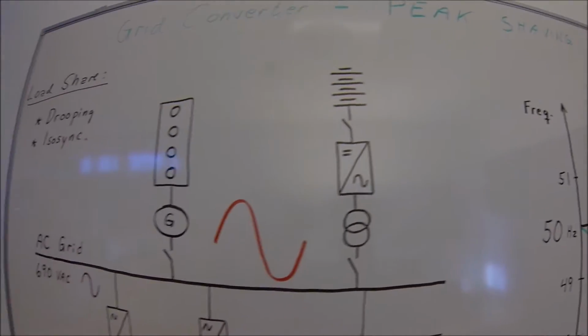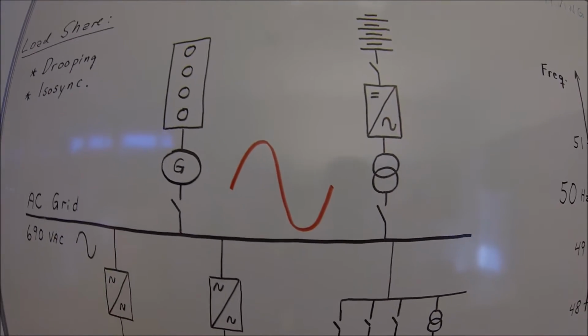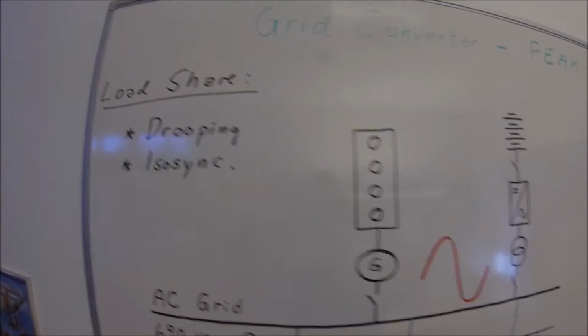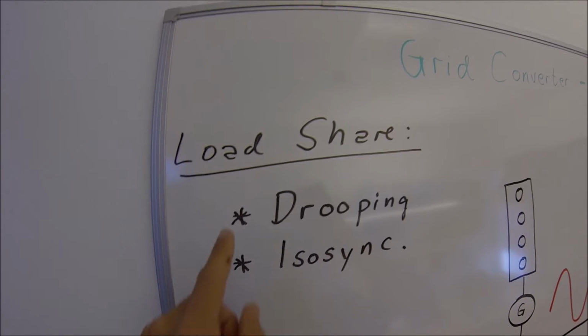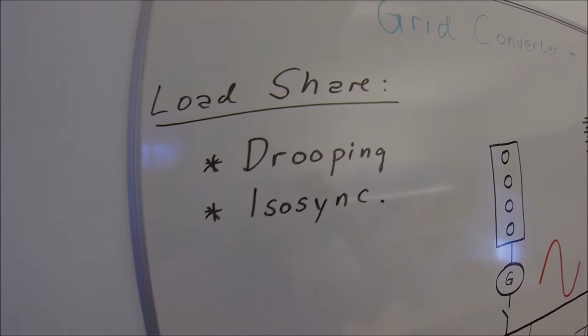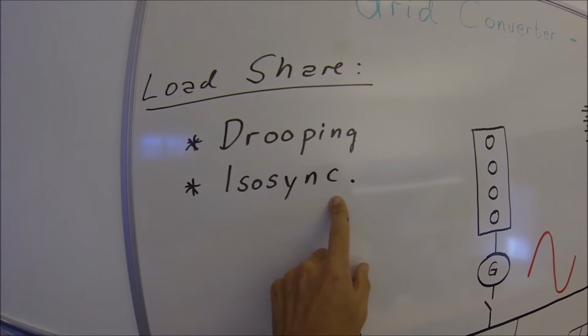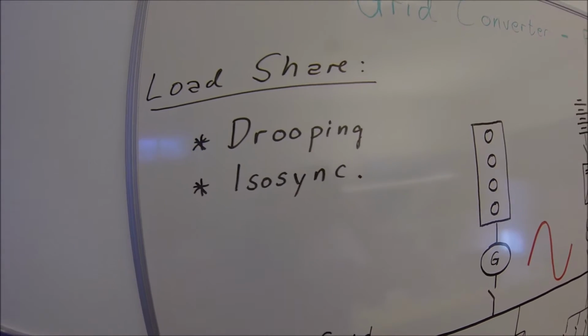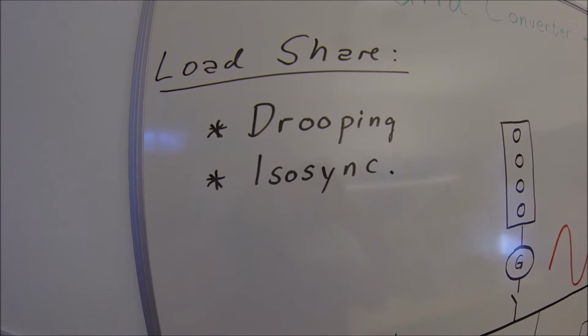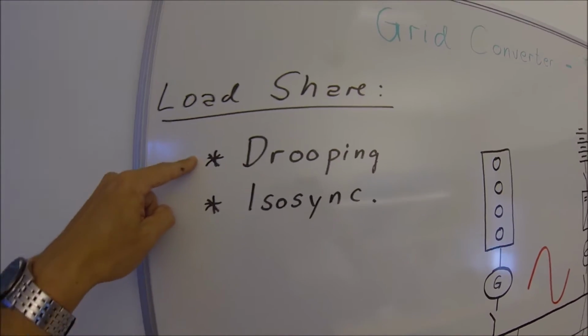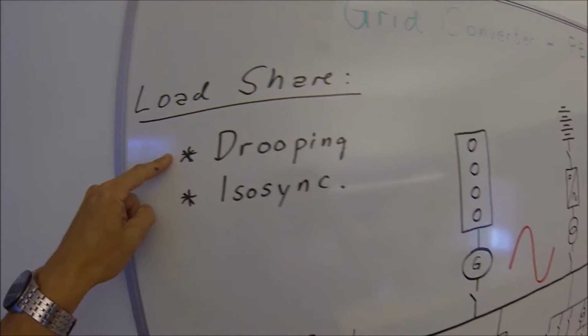Between the diesel generator and the battery, we need to have some kind of load sharing. This load sharing can be done in two ways. You have the traditional drooping and you have the isosynchronous mode, which are controlled with reference from the power management. First, take a look at the drooping function.